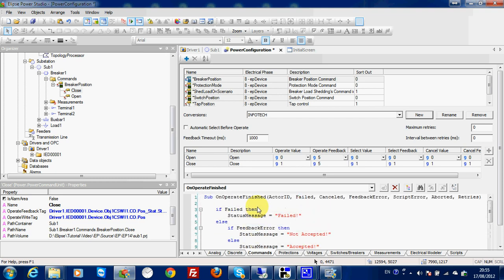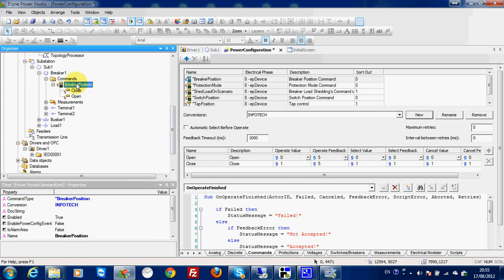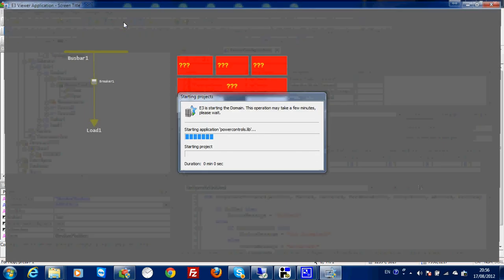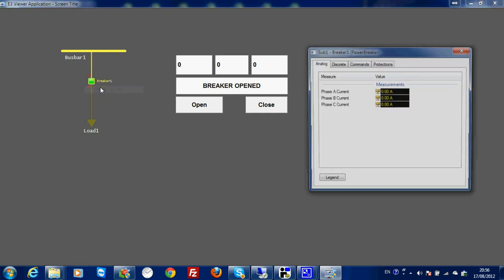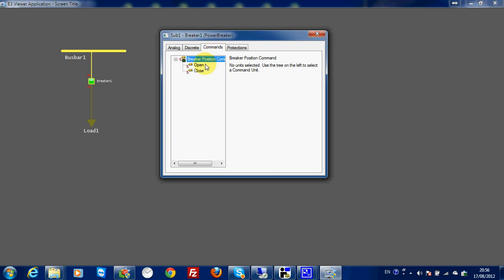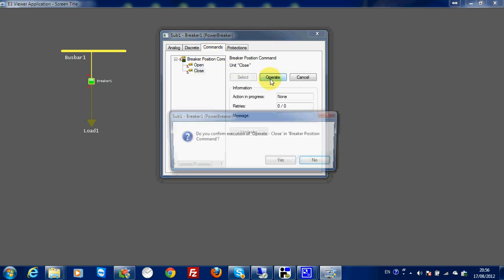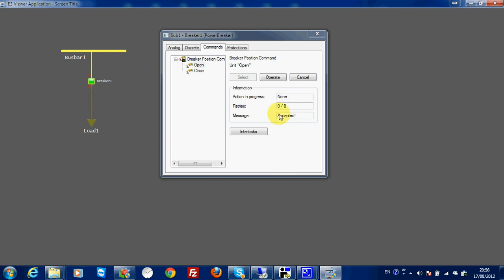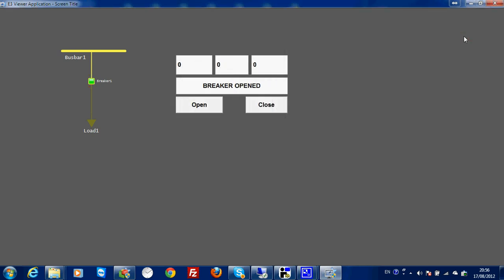The last thing is to check that my breaker position will also follow the 'infotech' conversion — so everything should be ready. Now I close the viewer and start everything. I go to my breaker, measurement, and then to command. I can close and then operate. Confirm, operate — yes, the command is accepted and the breaker is closed. Then I open, operate — yes, the command is accepted and the breaker is open. This is how you make the command by linking the driver to the breaker.